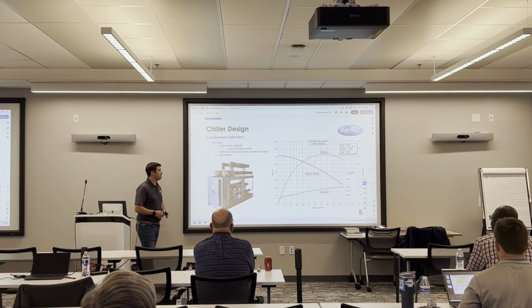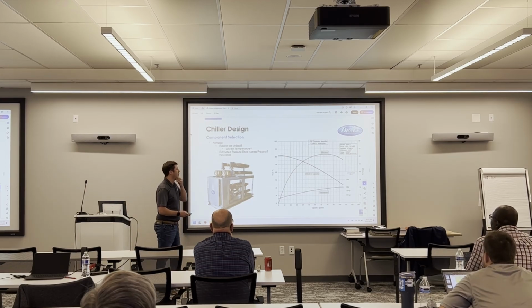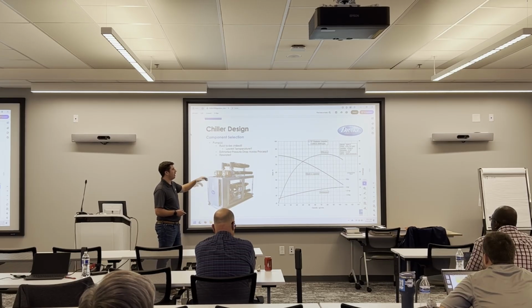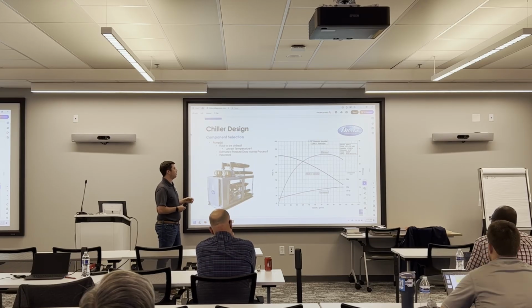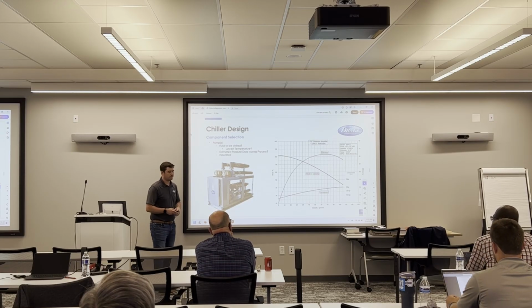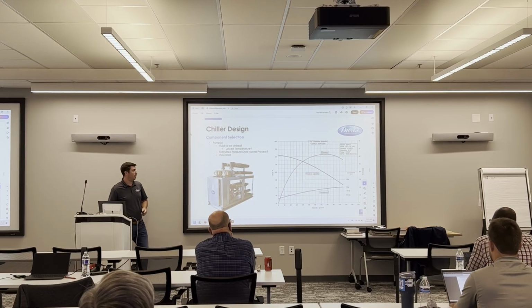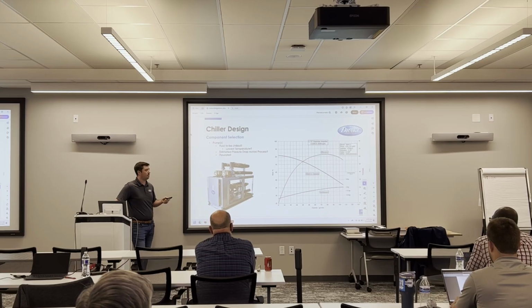And just some other things to note real quick. This is obviously a curve for water, so it's important to know what fluid it is that you're cooling. If you start to add glycol, that glycol is going to become viscous and essentially add an internal pressure drop. This curve is going to look a little different with glycol. It's going to have to be corrected, so to speak, because the fluid characteristics of that pump are going to change. So you're actually going to get less flow as you add a glycol solution or an antifreeze to this fluid with this specific pump model.